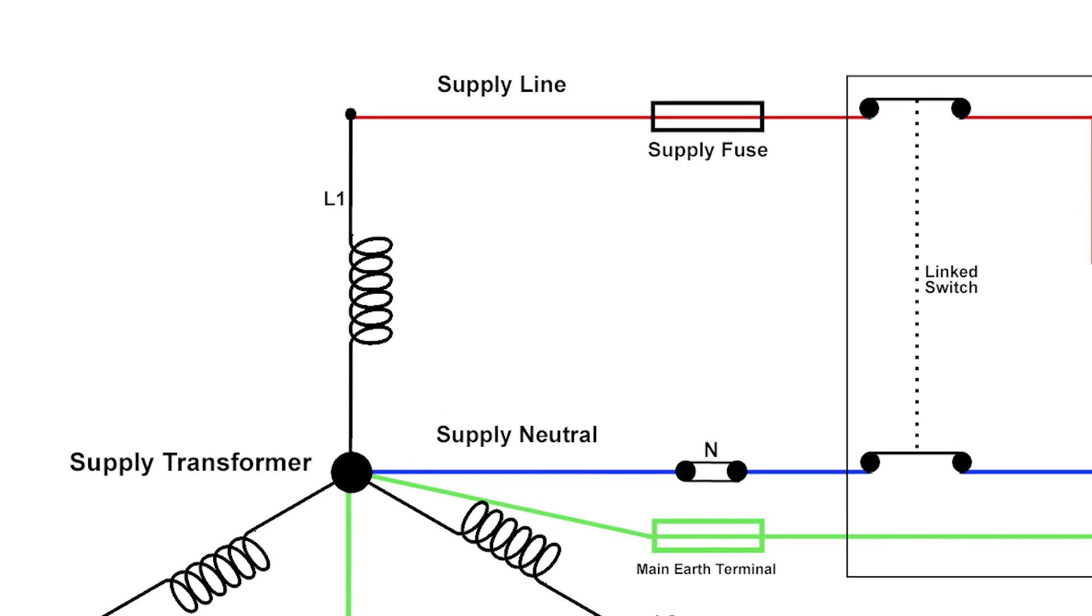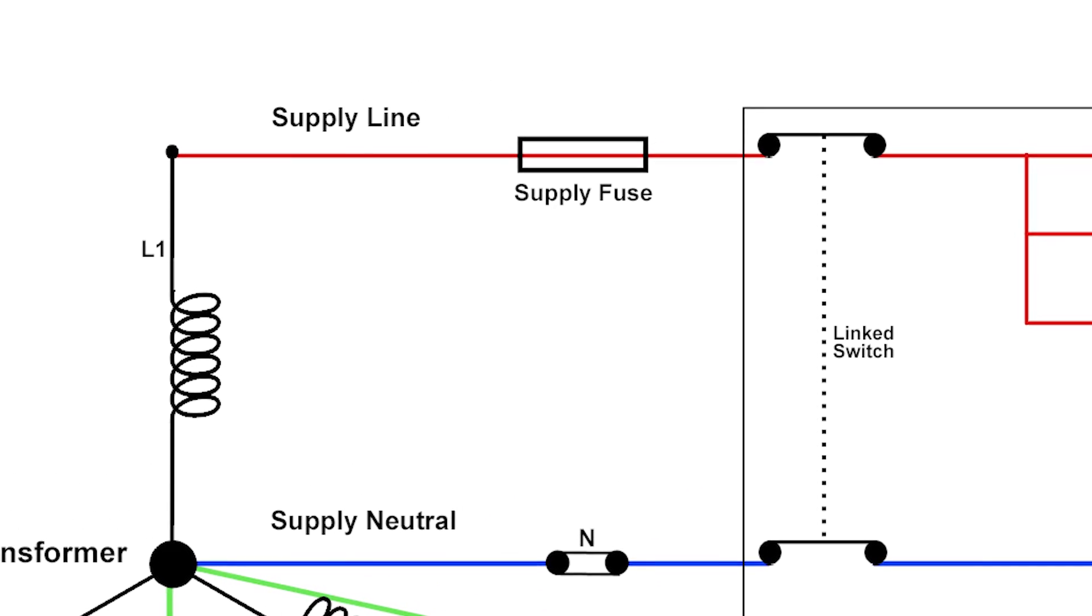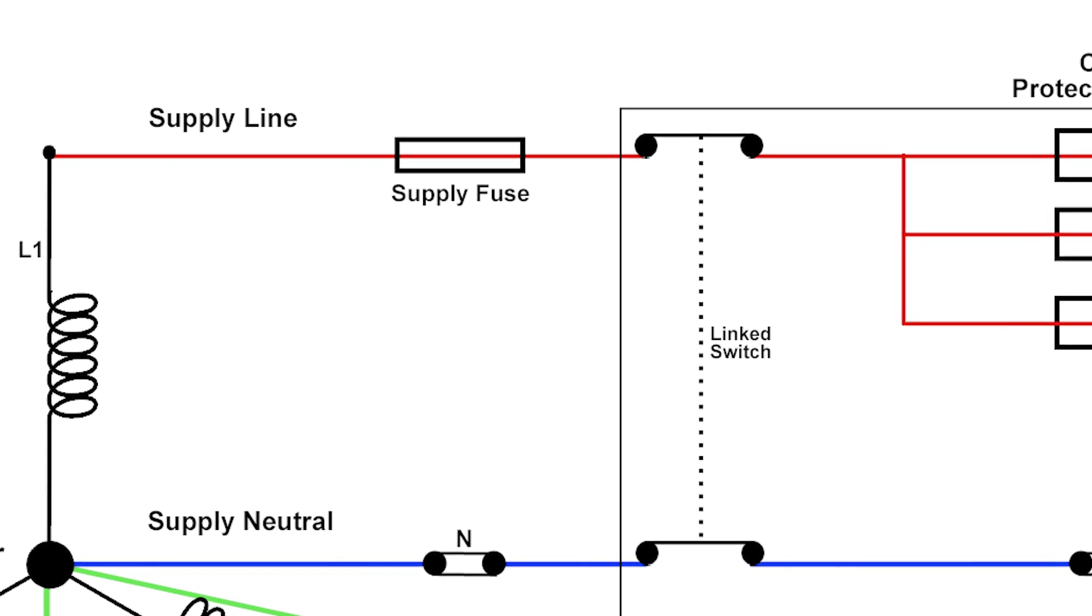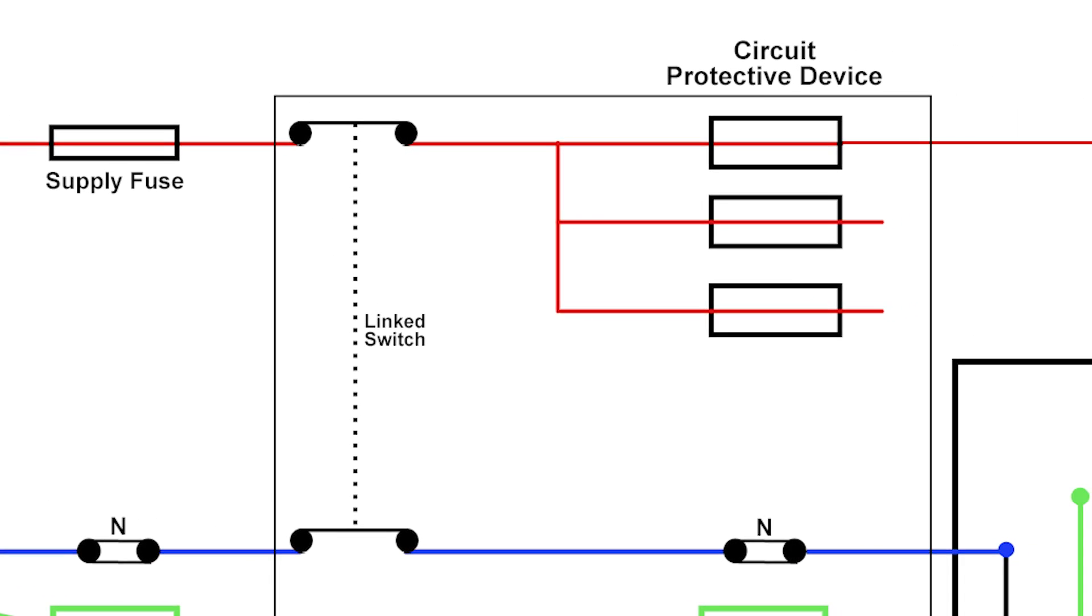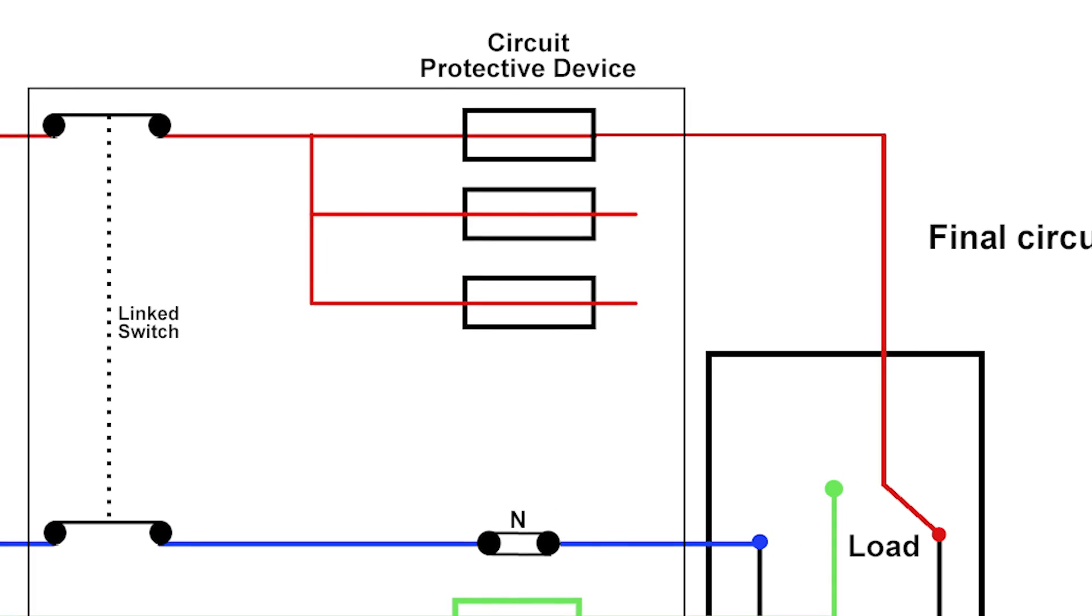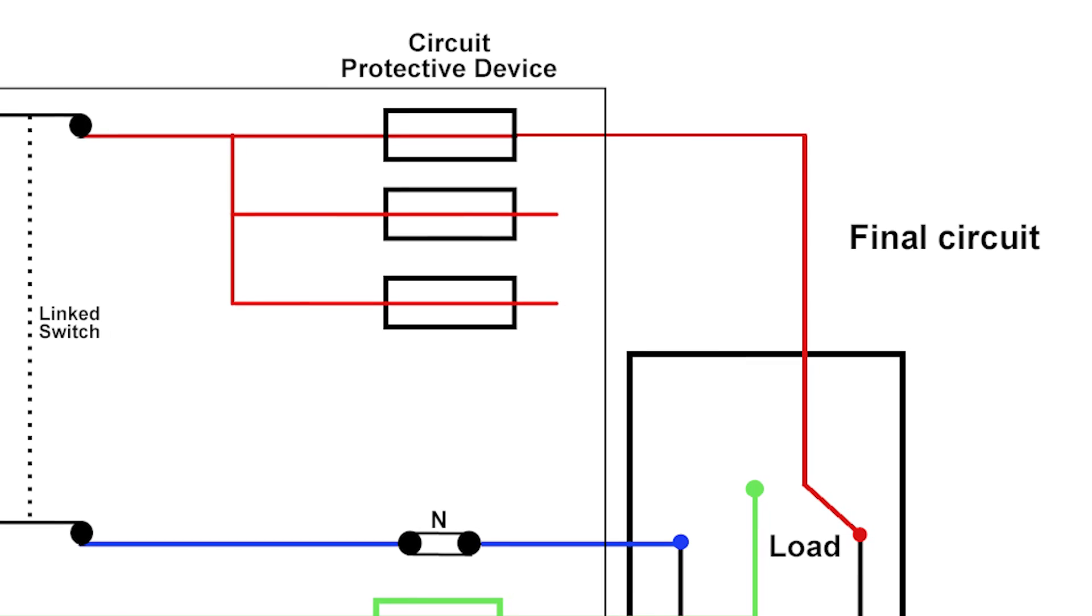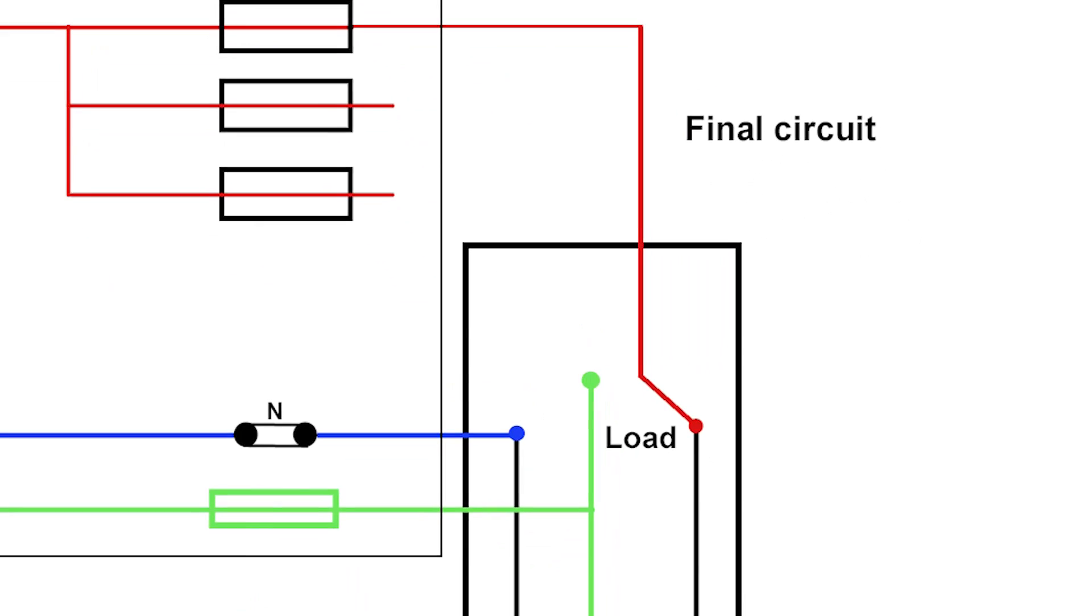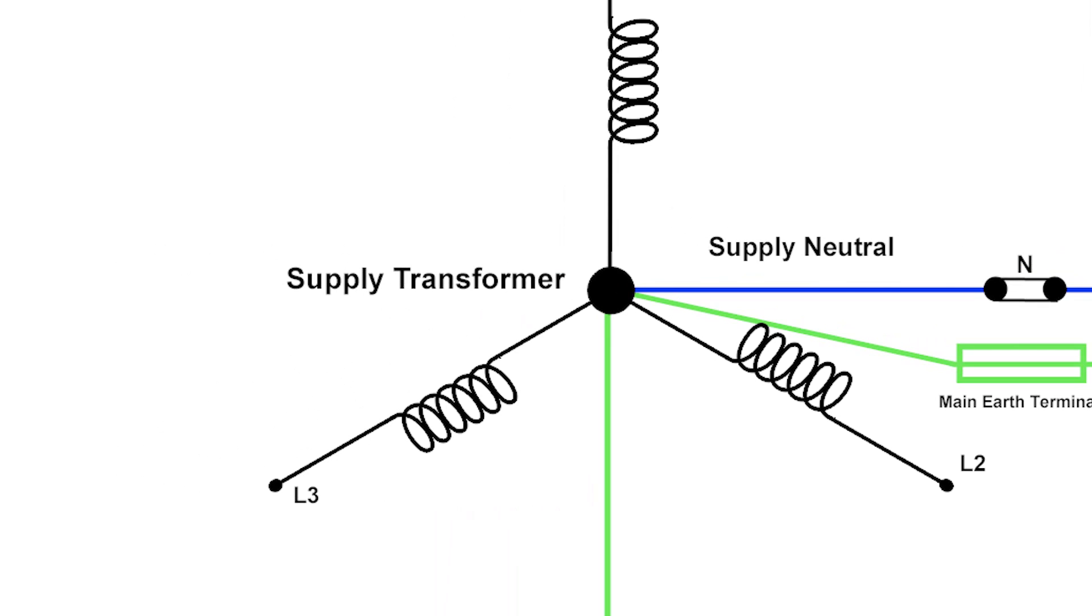Our current starts off at a pressure of 230 volts, flows into the building through this part of the system—this would be possibly our underground cable—then goes into a service head or a service fuse, through the service fuse to a main switch. Past the main switch we've got a consumer unit which will have a selection of protective devices in. If I connect a piece of equipment to the final circuit, the current will flow through the protective device, through the final circuit, through our piece of equipment, and through to the star point of our transformer, which is generally around zero volts.